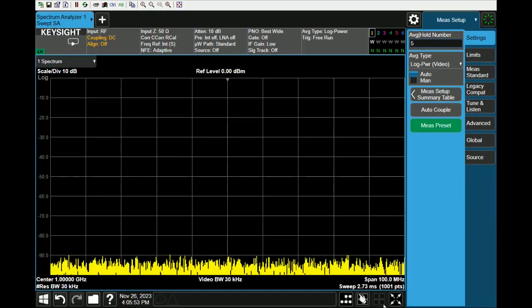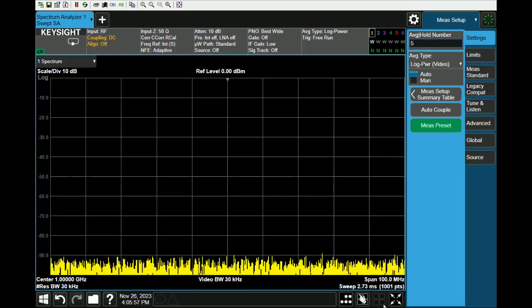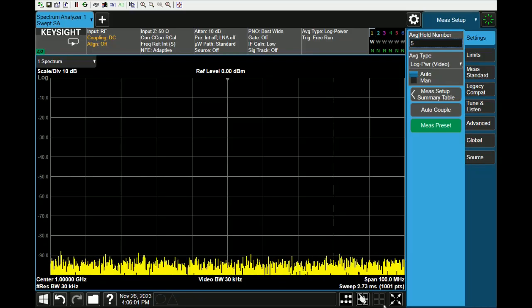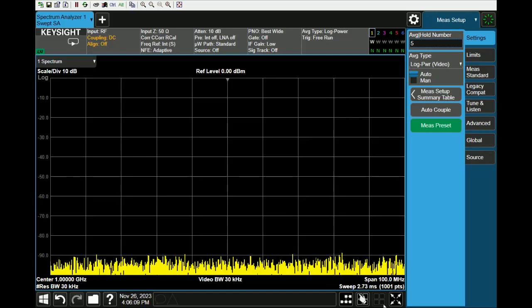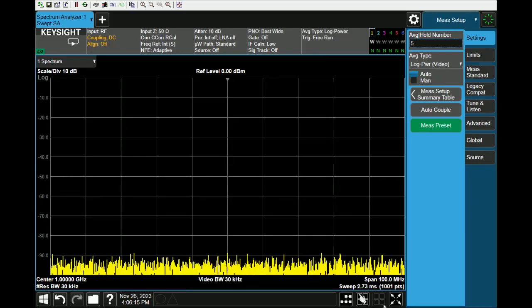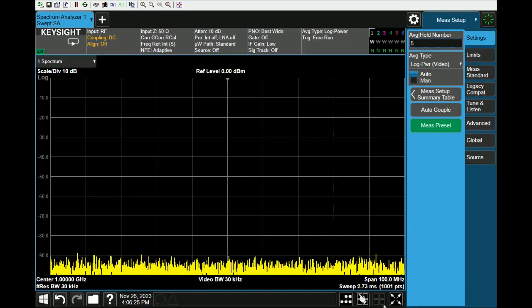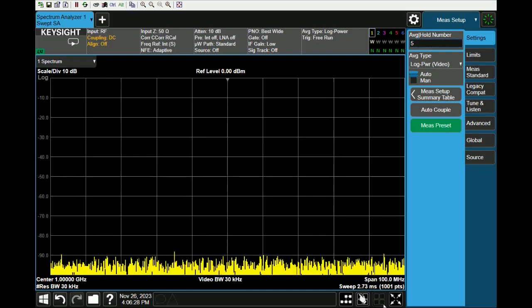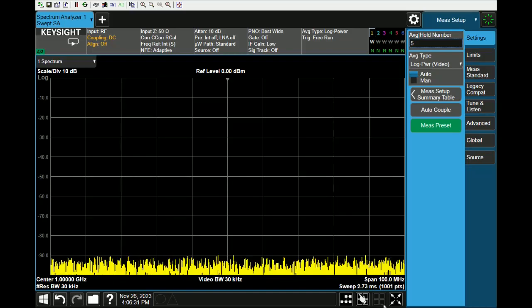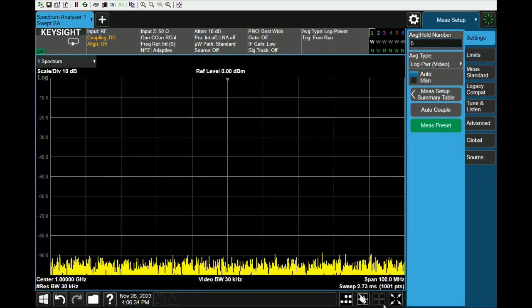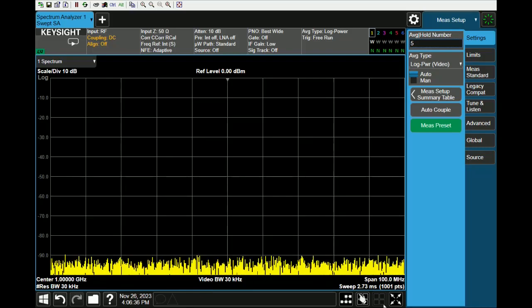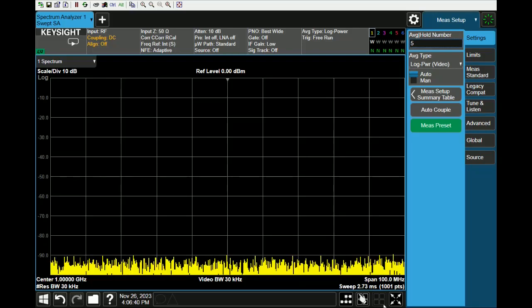In this video, I'm going to show you great features that I found recently on the Spectrum Analyzer family from Keysight that really helps me with the programming. If you have gone through some automation programming in controlling instruments, you'll be quite familiar with this group of programming language called SCPI commands. SCPI is essentially an instrument's language that when you send a command to the instrument will translate it to some steps, for example, changing the center frequency or changing the span automatically from your program. So this feature is what we call SCPI Recorder.